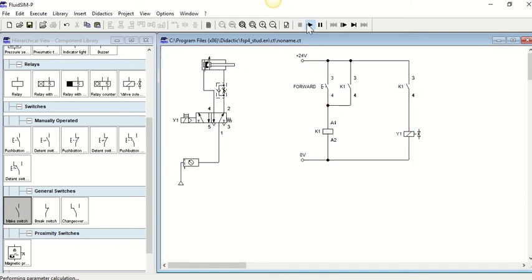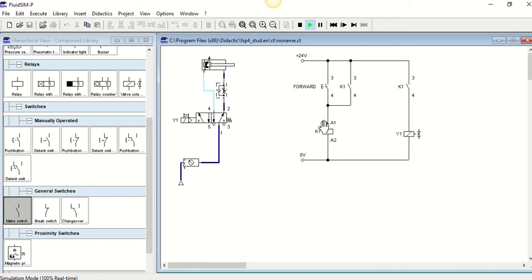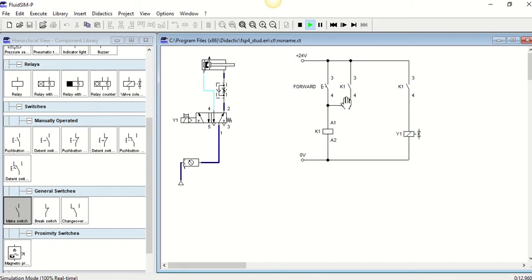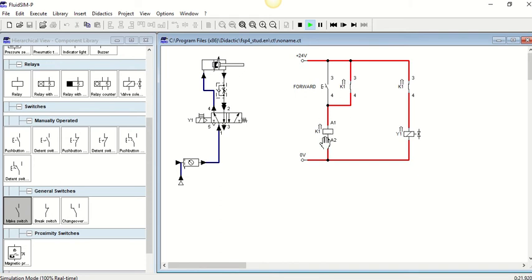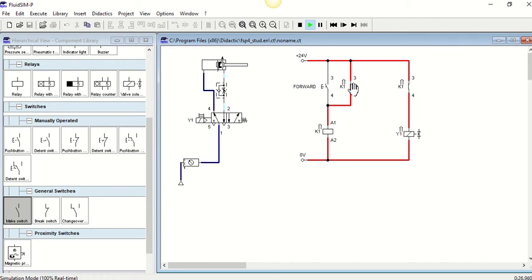Let me just step you through that again. The only way I can get power to K1 is by pressing this forward button. Why? Because this K1 and this K1 will only ever come on when this is energized. So it can never start going through this way. It will always just come through this way. But once we have given it that, this closes over, and then it provides a constant path to keep the energy flowing there. And that is what we call latching it on.